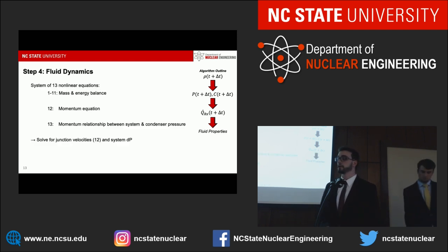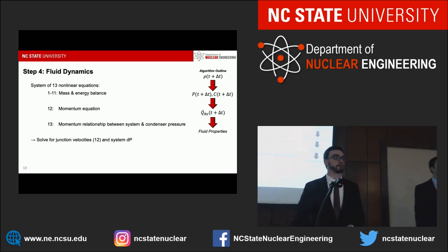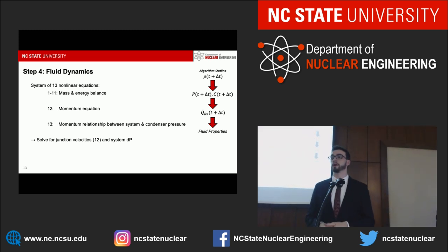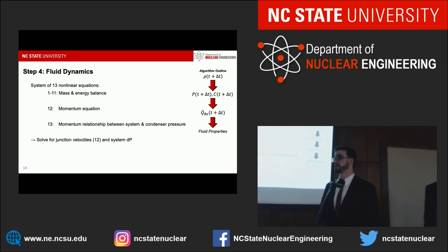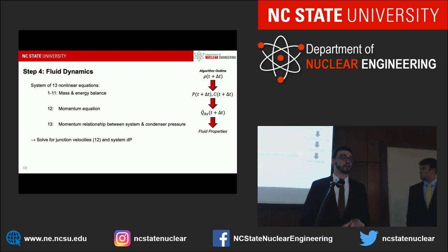And then to solve the fluid dynamics, we looked at mass and energy balances in each of the 11 nodes of the core schematic that Matt showed earlier. We also looked at a momentum equation integrated around the full RPV flow loop, and then a momentum relationship between system and condenser pressure.